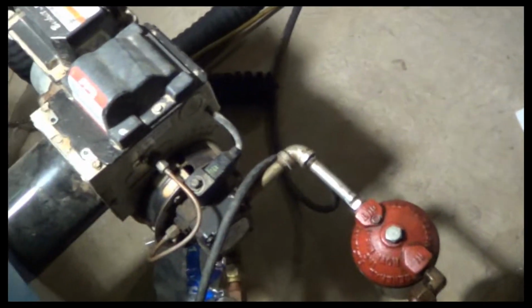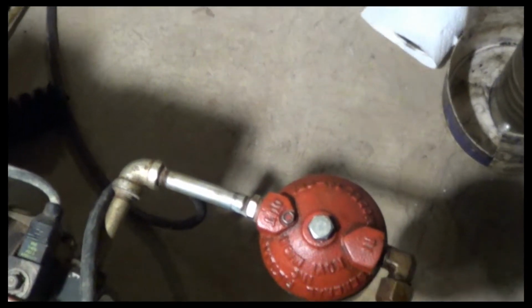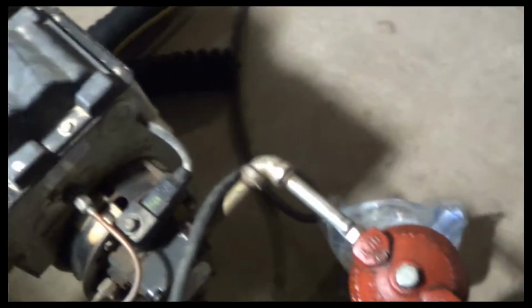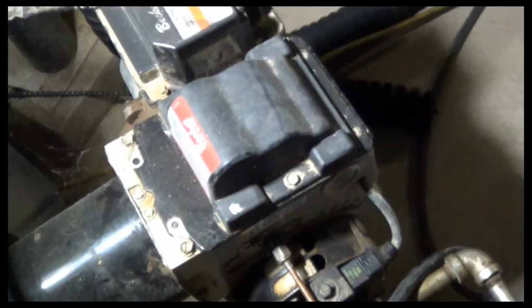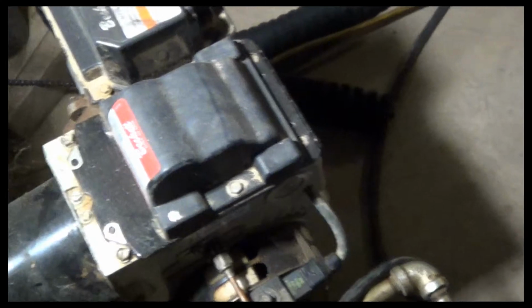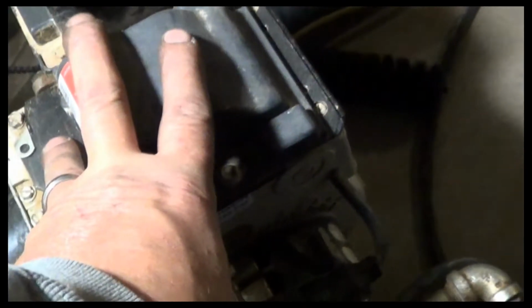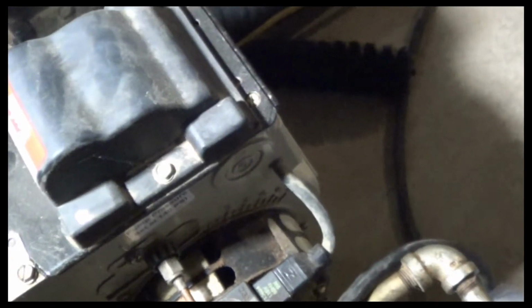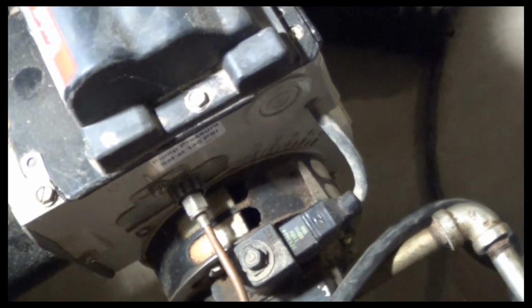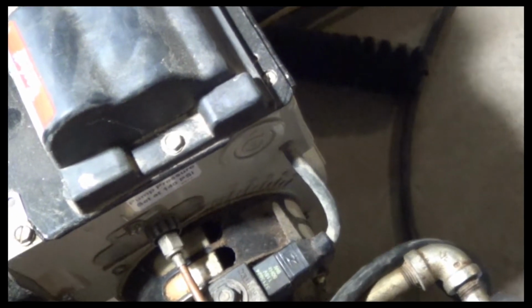What I'm going to do next, I'm going to change the oil filter. I'm going to put a new oil filter in. I think everybody knows how to change an oil filter. It's no biggie. I'm going to change the nozzle, which is inside the burner. That's got to be done during a clean and check. Going to check all the voltage on the transformer, check pump pressure, make sure the pump's up to what it should be doing, and check the CAD cell relay. Make sure everything's working in the relays. That's what operates the boiler.